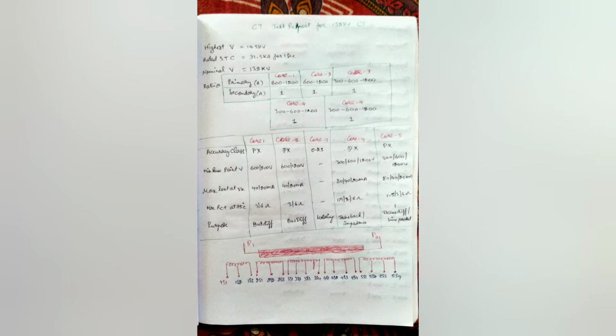Next is the accuracy class. The CT accuracy is mentioned as metering or protection, or 5P10, 5P15 kind of protections. All that is mentioned in your accuracy classes only. So core 1 and core 2 have special protection, which is mentioned as PX, and core 3 has 0.2S, which means it's a metering core, and core 4 and core 5 are also a protection class.